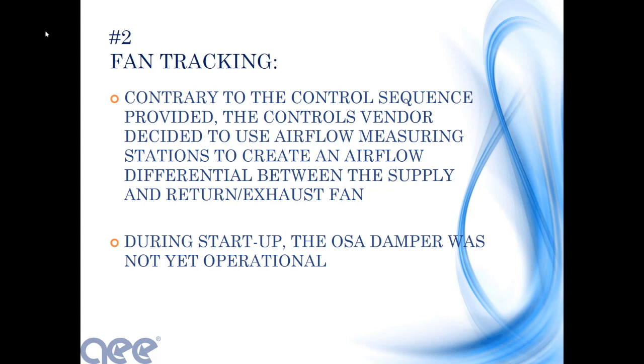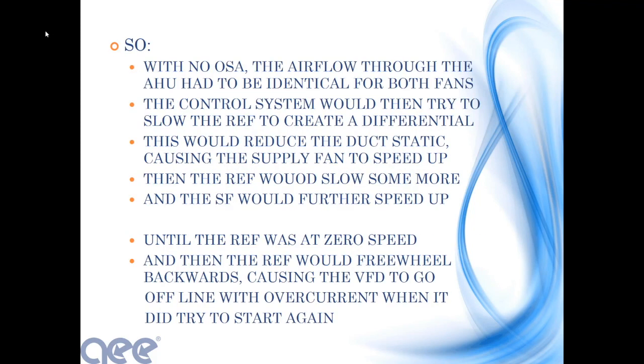Now, he had a little problem. He was trying to put this thing online, and he hadn't yet got his outside air damper operational. And it was a high-quality air handler. When that damper was closed, it didn't leak. So here's what happens. No outside air. The airflow coming in the return, going through the return fan, going through the coils, going through the supply fan, it's the same airflow. It can't be anything but the same airflow.